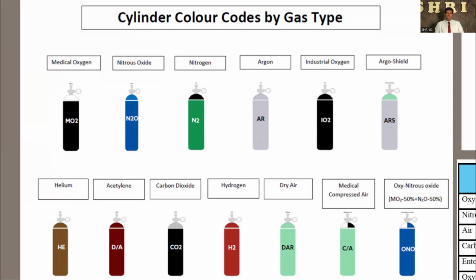So when the colors are wearing and tearing, sometimes it is very difficult to demarcate between oxygen and carbon dioxide cylinders, because when the white color one gets dirty, it looks somewhat like ash color. So it's our duty: if the color is not clearly visible and more than 20% of the body color of the cylinder has faded away, please label it as in need of repainting.